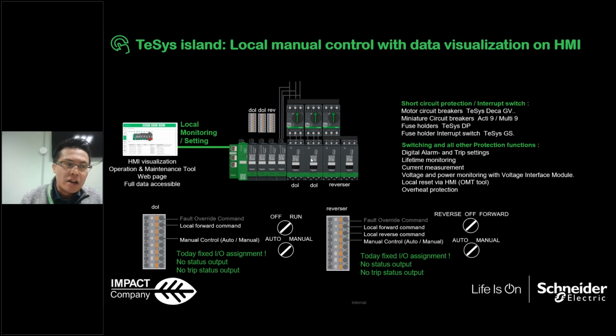Or, for the TeSys island, each bus coupler has an embedded web page. So you can use your computer to connect to the bus coupler, input the specific IP address, and go to the web page, what we call the operation and maintenance menu. You can see all the energy data and control locally with this web page. So every bus coupler is embedded with a web page of the TeSys island. You can switch on all the other protection functions, the digital alarm, the lifetime monitoring, and current measuring with the HMI. So this is the local control.